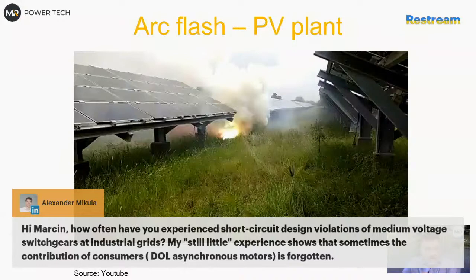But I had a recent project with a lot of big companies where they generally had to change the rating of breakers and switchgears a few times before I finished the study. So yes, it happens even with a lot of people involved, because they didn't take into account a lot of motors, generators, or the operating modes. So motors, generators, battery energy storage systems, and PV systems are sometimes installed, and UPS systems - though for UPS it's a little different because it depends how they work.